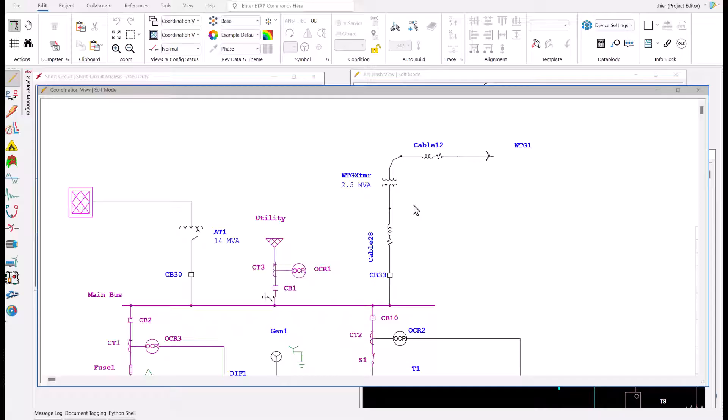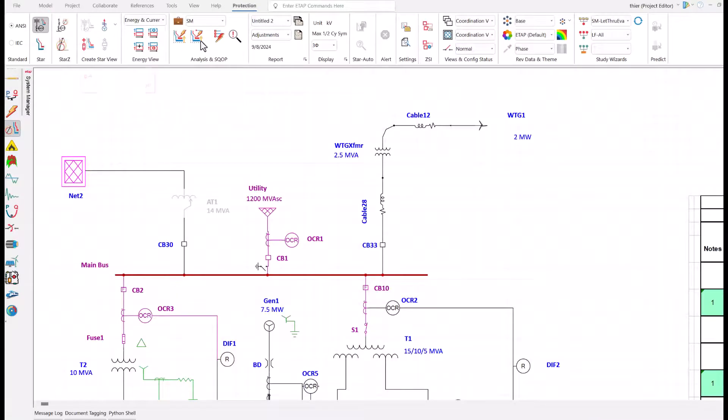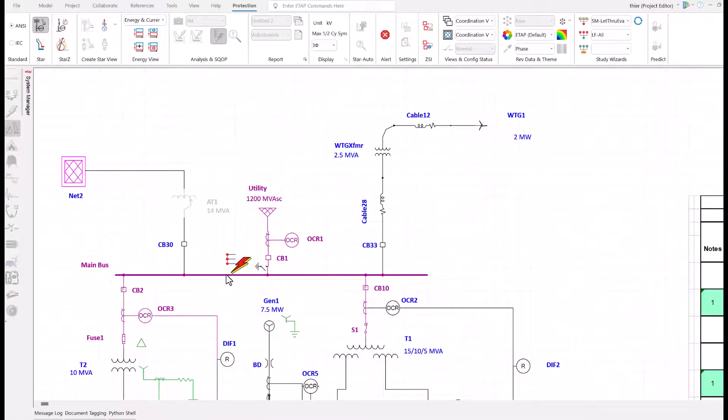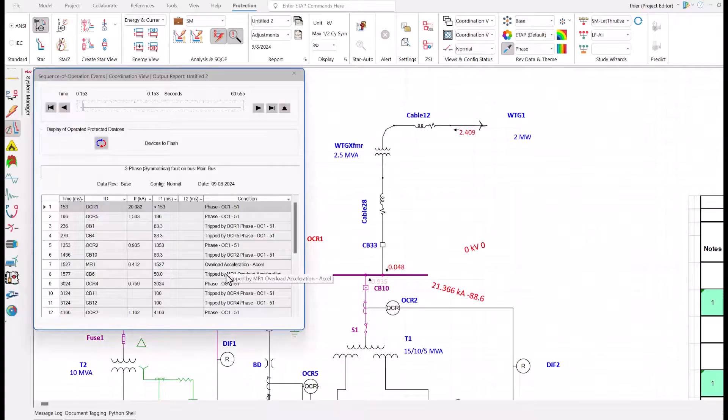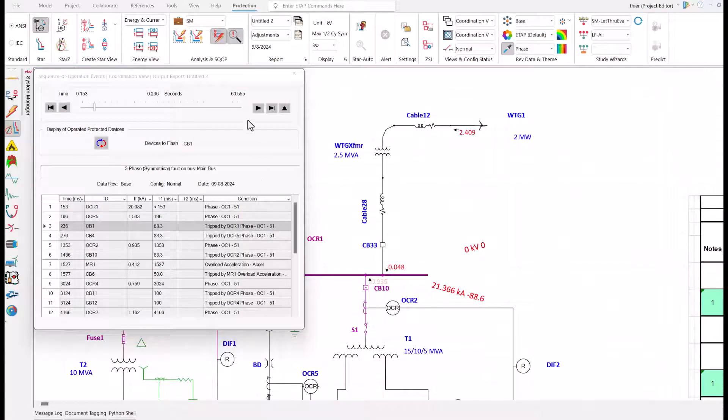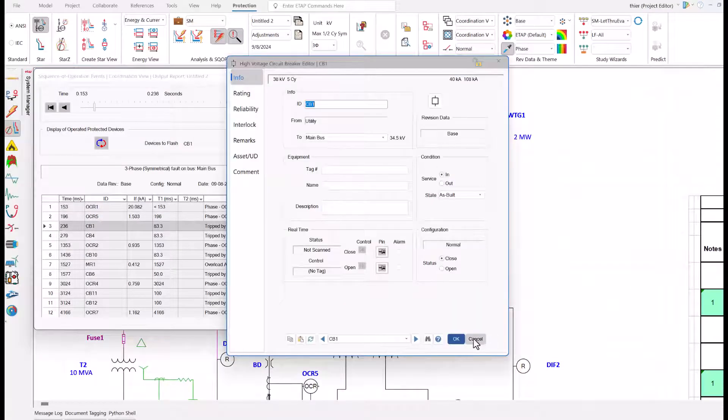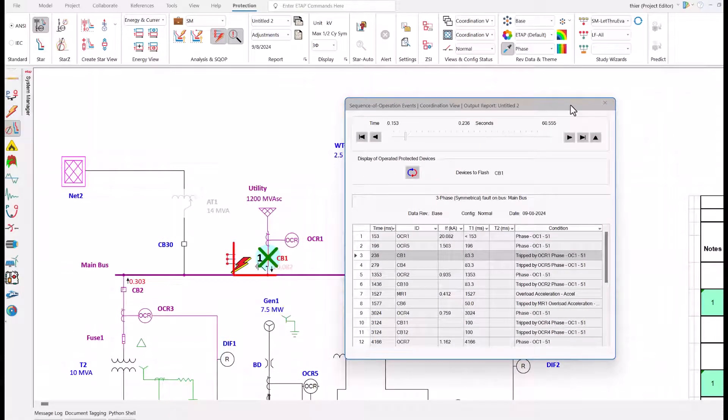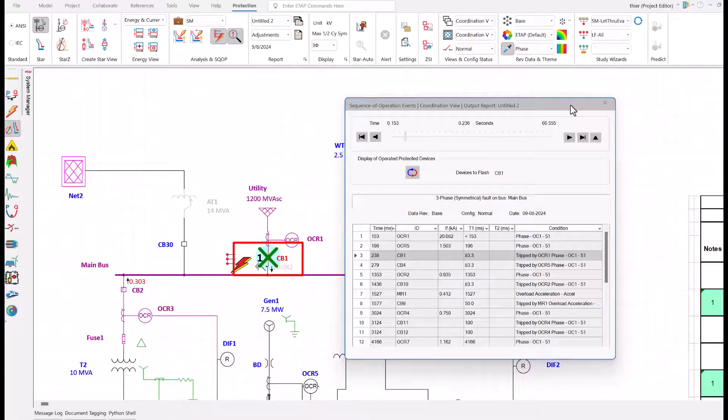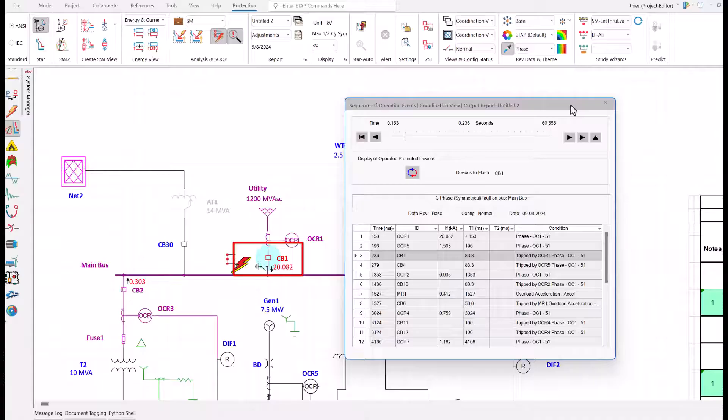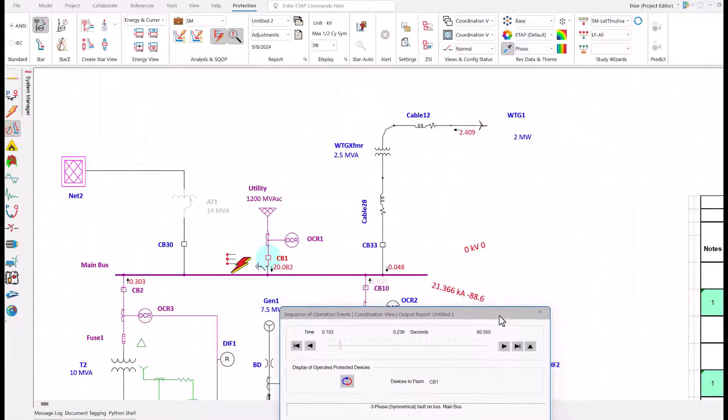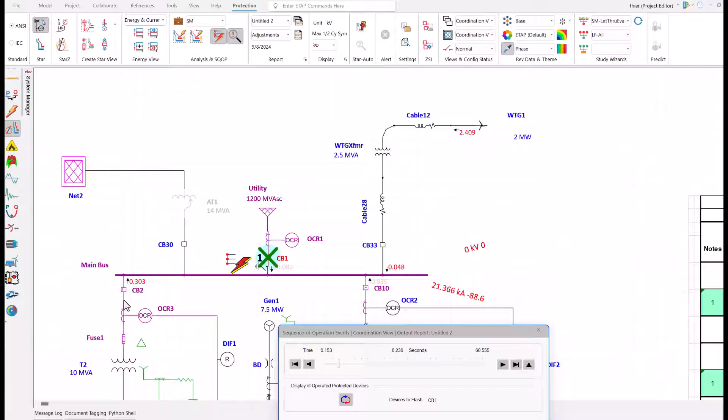Due to the presentation time limit today, I won't delve into the protection part. However, I will show you coordination. ETAP has a cool feature called Sequence of Operations. We will see if the protective devices are coordinated. I placed a three-phase fault at the main bus. You can see the first breaker that opens the fault: CB1. That is what we want. We are coordinated. However, there are three additional paths for faulted current. This sequence list will show you when each breaker opens and we can then conclude if we have appropriate coordination on those breakers.